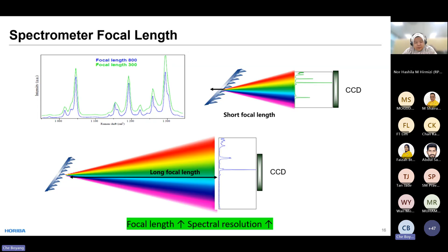Once you already have a Raman microscope, the focal length is actually fixed. You cannot really change it anymore. Then how are you going to improve your spectral resolution? This responds to the second parameter of your spectrometer, which is the grating groove density.